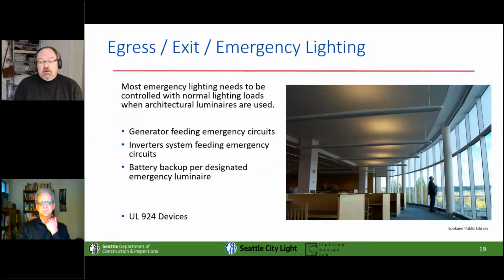When we're talking about LLLC or NLC network lighting control systems, we have UL924 devices. A 924 device is essentially a shunt relay. It can be part of the lighting control system itself if it's UL listed that way, or it might be a third-party system taking both normal and emergency power. When it senses the loss of normal power in one of several ways, it will immediately drive the load to full, and it will stay there for a period of time, even after normal power resumes, so that we make sure we ride through the emergency event.